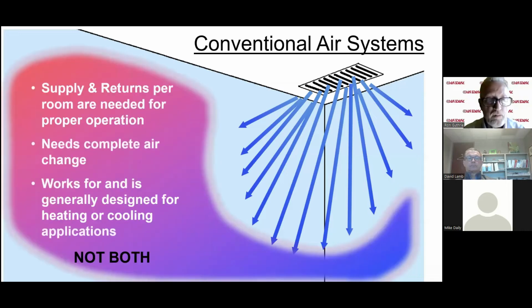In our conventional systems, we depend upon throw and diffusion and return air. We depend on room air changes to move our air around the room. In this type of system, if we have a ceiling register as shown here, that's great for cooling. It's not very good for heating. All right, and likewise, when we have them in the floor, that's great for heating, but not very good for cooling. Diffusion and throw is more important in that aspect, right? So where we put the registers in a conventional system is not good for both applications.